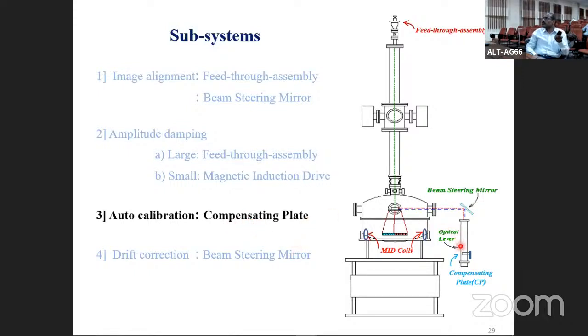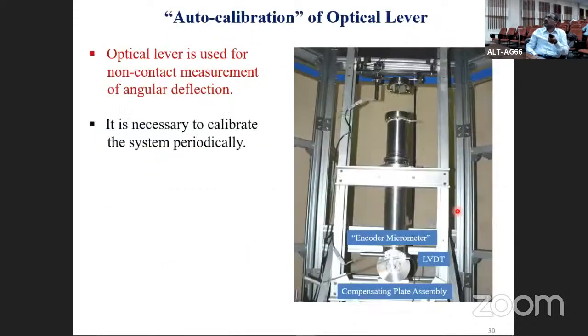What we use is a compensating plate to calibrate our optical lever here. As again I said, optical lever is for the non-contact measurement. It is necessary to calibrate the system periodically. See, everything has a drift associated with time, and whatever best you try to eliminate all the effects, they will still be there. So it's a good practice to periodically calibrate your system, whether it's an instrument or some measuring device like an optical lever or your control systems or whatever it is.